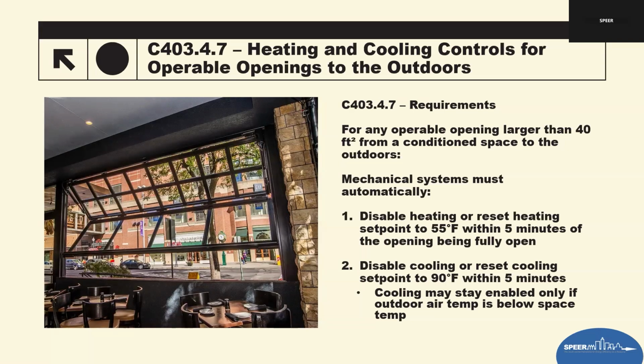The intention is to prevent heating and cooling from running when large amounts of conditioned air can escape to the outside. So with heating response, the system must disable mechanical heating or reset the heating set point to 55 or less. This ensures the building is not trying to heat when the door is open. So if it's 62 degrees outside, you don't really need heat, but it's below its set point, then when these doors go up, the heating set point goes to 55. So you're not actively heating. Same for cooling. It must disable cooling or reset the cooling set point to 90. So same thing there. If it's 85 degrees outside or 78 degrees outside, the doors are opened up, you don't really need air conditioning. It's going to set it to 90 so it doesn't accidentally come on.